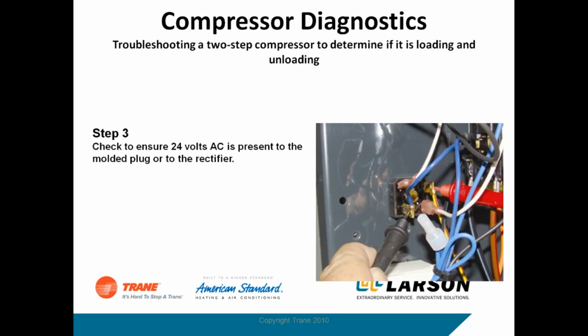Okay, so on two-step scrolls, you're going to find a rectifier, usually on the wall inside the control panel. It's going to have a yellow and a blue wire, and then it's going to have two white wires, okay? If you look at the rectifier, there are two white dots on there. That's where the two white wires go, and those are DC. So what we're doing is taking 24 volts AC, running it through the rectifier, and dropping it down to 15 to 18 volts DC on those white wires going to the solenoid in the compressor. And that's what your Y2 does.